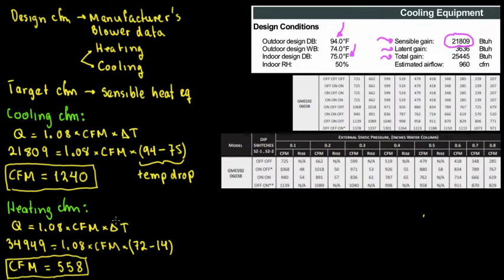As you can see, the cooling CFM is significantly higher. The first step for duct design is to make sure there is enough CFM for all registers and supplies. That's why we take the cooling CFM into account for duct design. If the system can provide this amount of CFM, it will of course also comply with the heating CFM requirement.